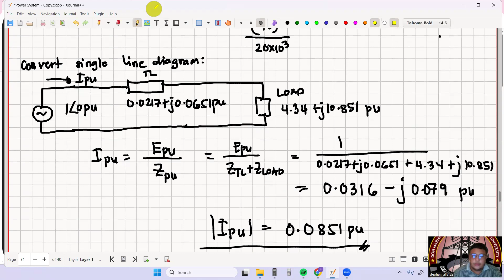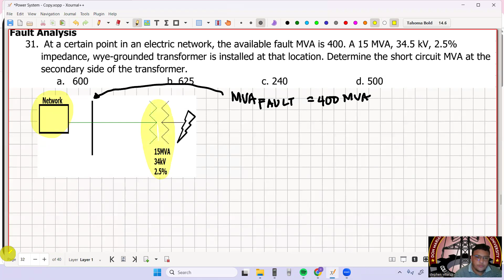Okay, so at a certain point in an electrical network, so ito yung network natin dito. The available fault MVA is 400 MVA. So now a 15 megavolt ampere, 34.5 kV, 2.5% impedance Y grounded transformer is installed at that location. So ito yan, yung transformer na yan. Kulayin ko na lang ng blue.